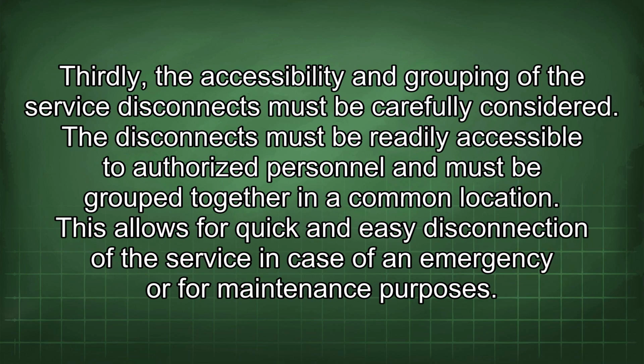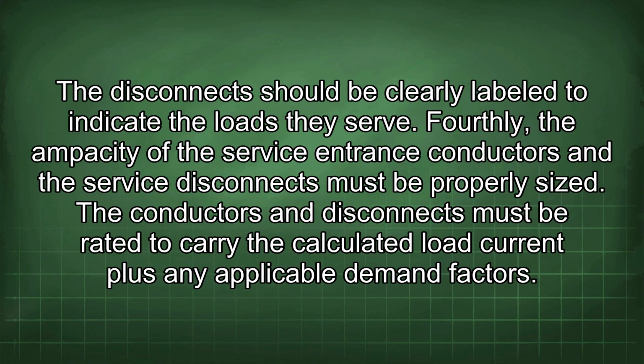Thirdly, the accessibility and grouping of the service disconnects must be carefully considered. The disconnects must be readily accessible to authorized personnel and must be grouped together in a common location. This allows for quick and easy disconnection of the service in case of an emergency or for maintenance purposes. The disconnects should be clearly labeled to indicate the loads they serve.